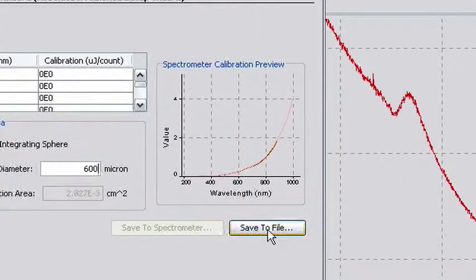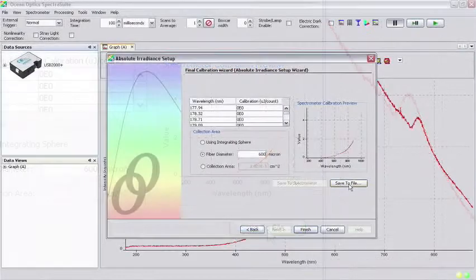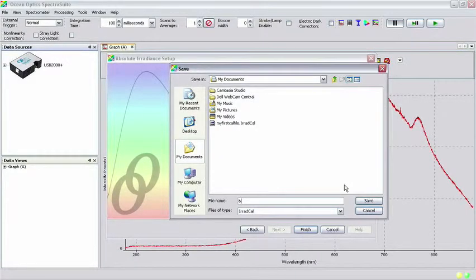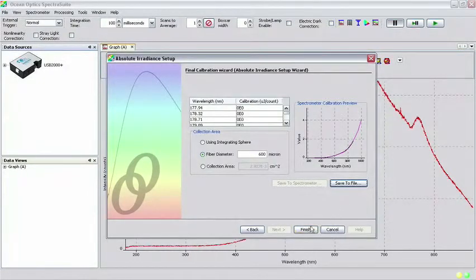The spectrometer calibration preview frame should show two lines of different colors nearly on top of one another. This indicates that the calibration file and the measurement of the lamp that generated the calibration file are in agreement. SpectraSuite generates a calibration file for your spectrometer at the end of the Absolute Irradiance wizard. To save this file for future use, click Save to File. Give the file a name and save it to the location of your choice. Clicking Finish brings you back to the main SpectraSuite window.